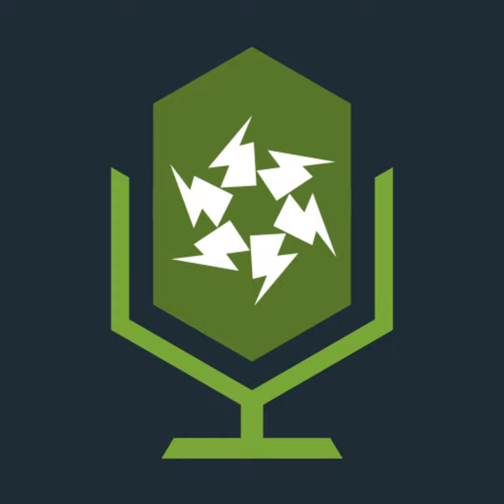It gives us the symbol, the class 2 symbol, 412.2.1.1. The equipment shall be of the following types. It then tells us electrical equipment having basic insulation only shall have supplementary insulation applied in the process of erecting it. So if the equipment is basic only, during the erection process supplementary insulation will be applied to it where there's more risk exposed to it. But when we do that, it does illustrate the symbol, which is the earth symbol with the cross through it, telling us that we must not earth this equipment.